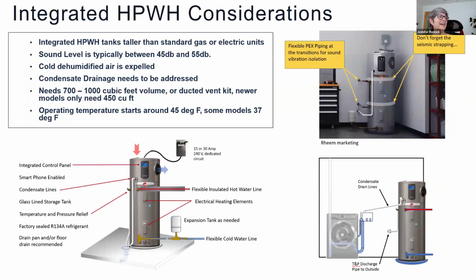And then slide 35 - you can send your discharge pipe to the outside, but for your condensate drain line you give an air gap just like you do for your washer, and you could put it in that washing machine drain box. There's not a lot of condensate that comes off of them, depending on how humid the climate is around you, but it does need to go somewhere.